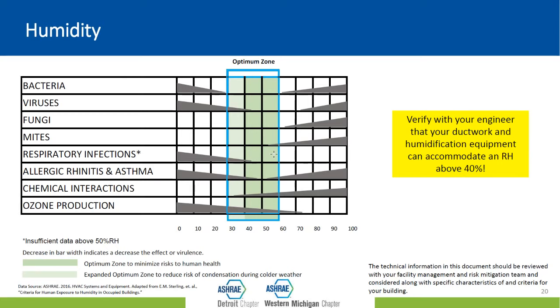So we want to be able to maintain those relative humidities between 40 and 60%. Now, we need to make sure that our equipment, that our system, can handle that. Can the ductwork handle that? If we have humidification equipment in the building, does it have the additional capacity to be able to provide that?